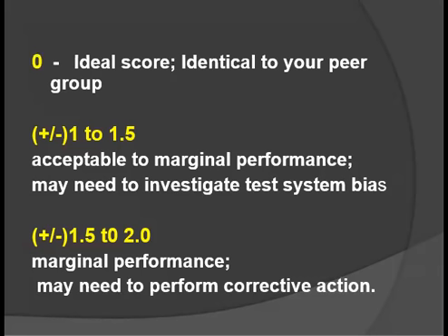So after calculating SDI, if the computation results to 0, that is the ideal score. In other words, this means that the data values of the laboratory are in 100% agreement with the consensus group or the reference method. So you can definitely say that the lab method that you are employing in the laboratory is accurate.